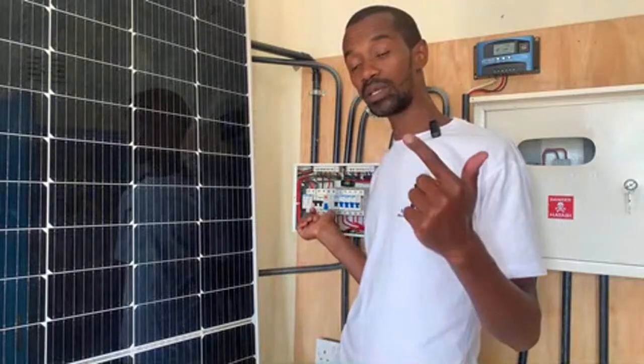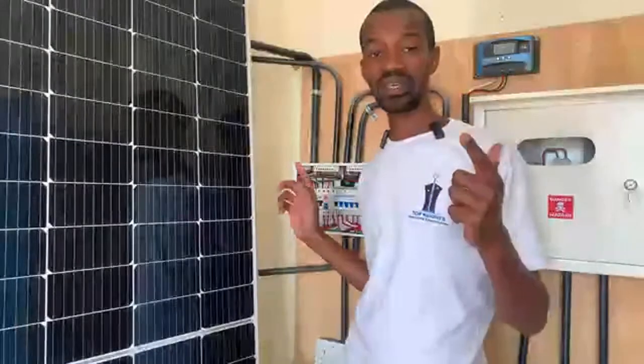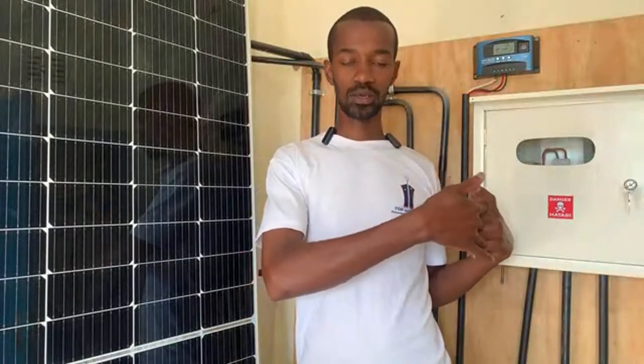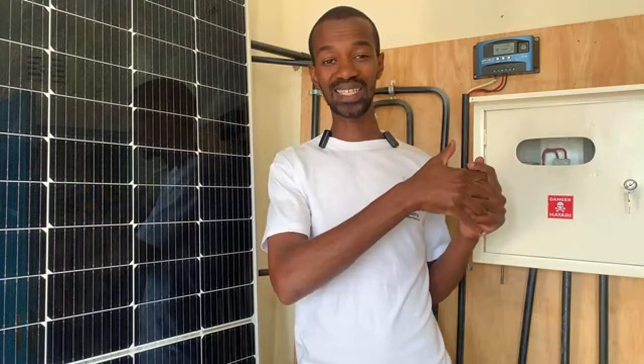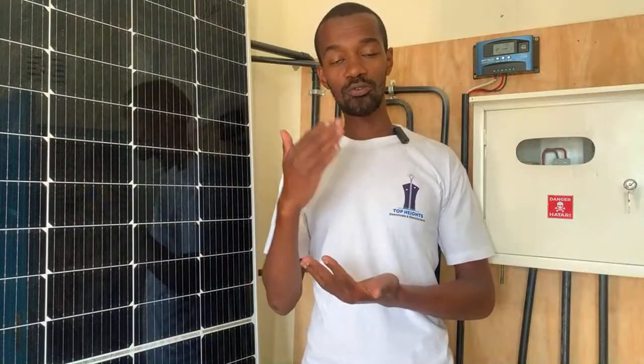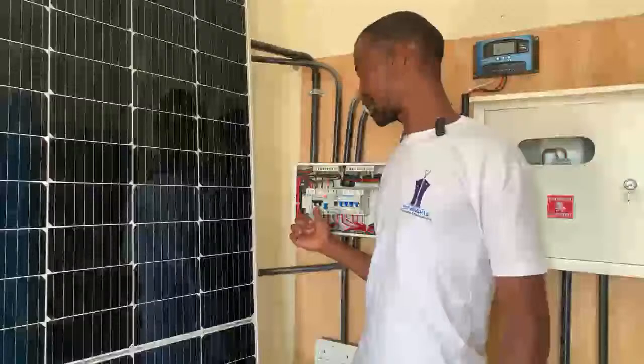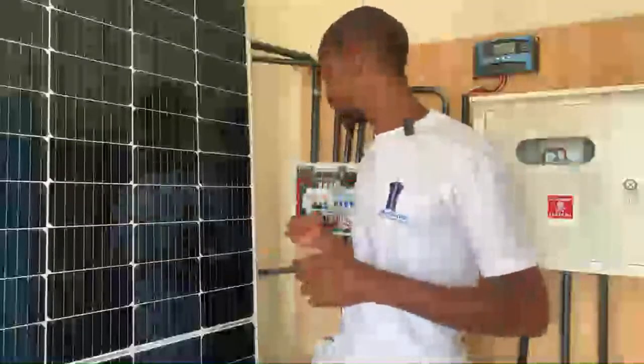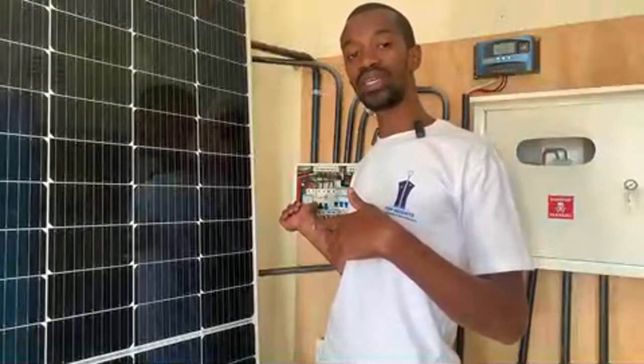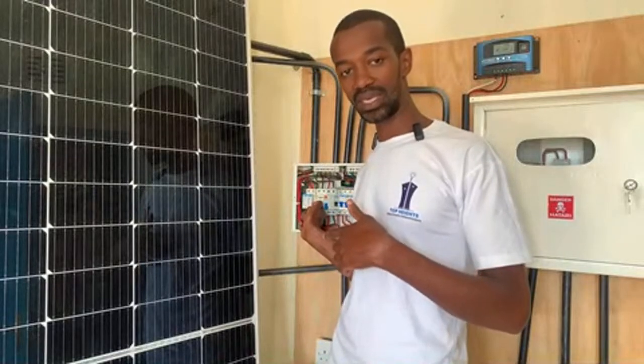I've done a good connection on the MCB, but if there is a loose connection on the main switch, there is a problem. Why? Because the main switch provides an output for all those MCBs, meaning it provides power for all the circuits in that installation, whether it's a house or a business premise. Current first flows into the main switch before it is distributed to the MCBs and further to the respective circuits. If the connection here is poorly done, there will be heating at the point of connection at the MCB or at the main switch.